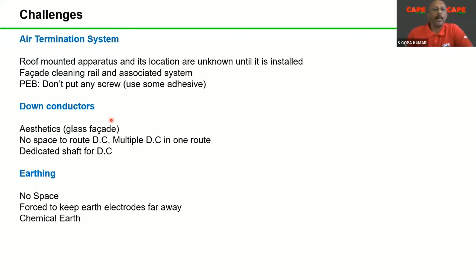The challenges which we face in every installation is most of the time when we get the drawing, the construction is already over. The structure is already over. And then they ask to make a design. And once when we tell that, sir, there is an important subject called separation distance. You have to keep your air terminal 1 meter away from the building or 2 meter away from the building. Nobody allows it. Then people always say, the other challenge, the roof mounted apparatus, because when we get the drawing, most of the time the roof is empty. But later we came to know that there are so many things coming up. Chillers are coming. The facade cleaning rail and its associated equipment are coming. That means probably the parapet you cannot use because something else is going to come. Roof mounted apparatus are unknown.